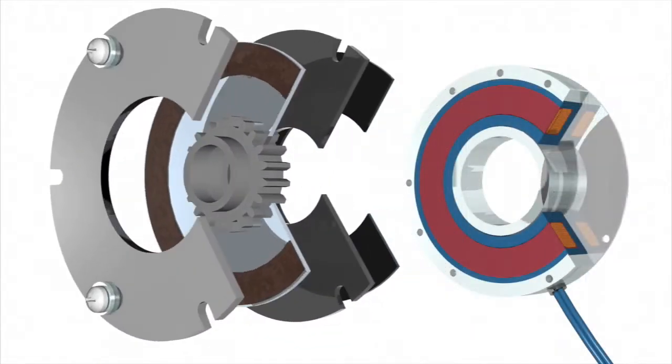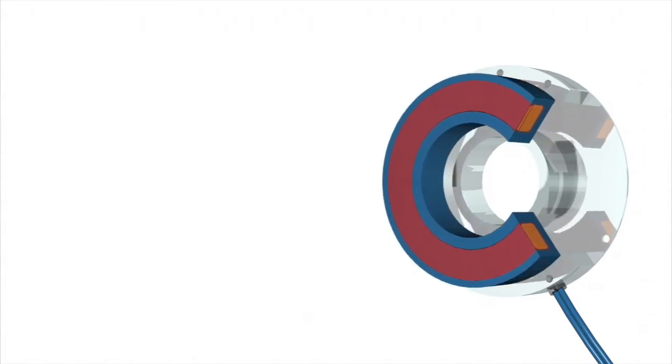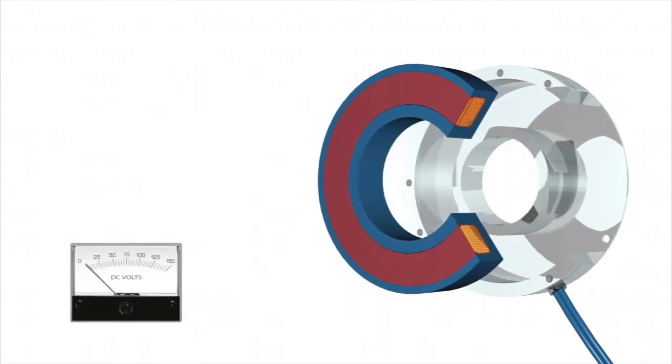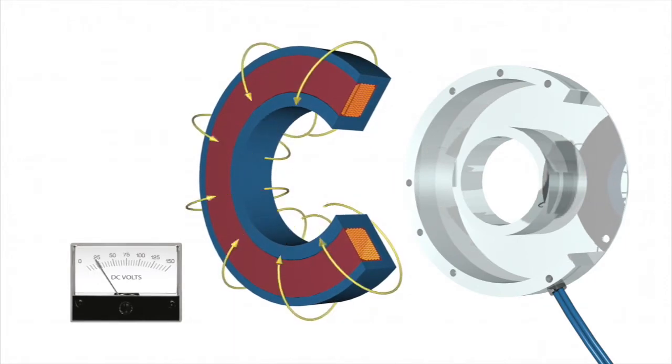Spring applied brakes transmit torque via spring pressure and use an electromagnetic field to release the spring pressure. Brakes are engaged mechanically and disengaged electrically.